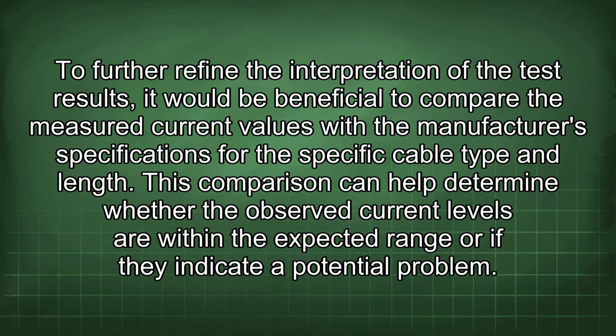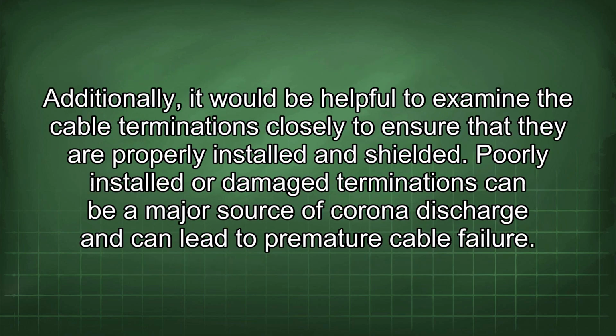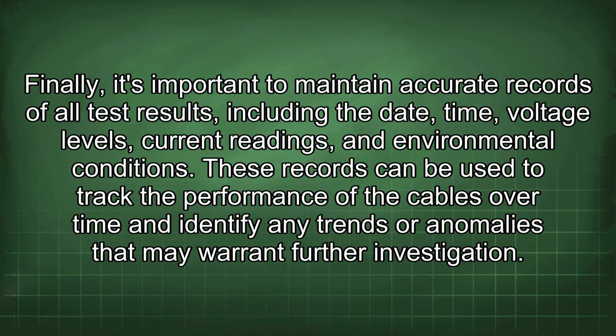To further refine the interpretation of the test results, it would be beneficial to compare the measured current values with the manufacturer's specifications for the specific cable type and length. This comparison can help determine whether the observed current levels are within the expected range or if they indicate a potential problem. Additionally, it would be helpful to examine the cable terminations closely to ensure that they are properly installed and shielded. Poorly installed or damaged terminations can be a major source of corona discharge and can lead to premature cable failure. Finally, it's important to maintain accurate records of all test results, including the date, time, voltage levels, current readings, and environmental conditions. These records can be used to track the performance of the cables over time and identify any trends or anomalies that may warrant further investigation.